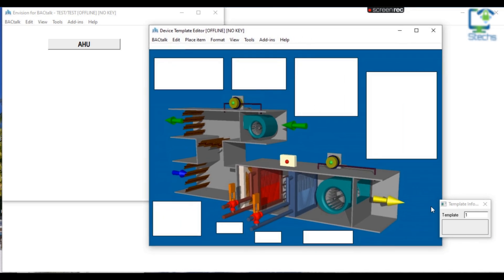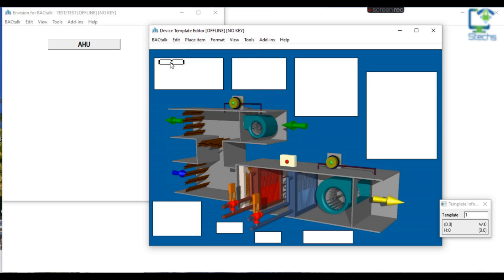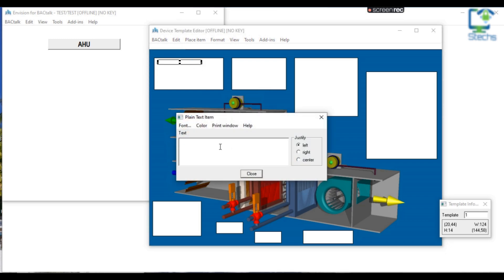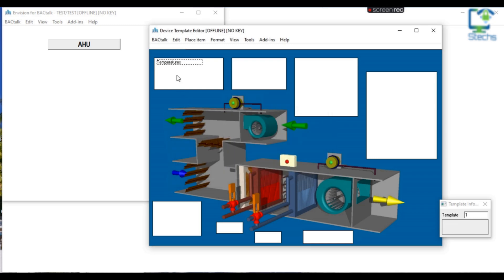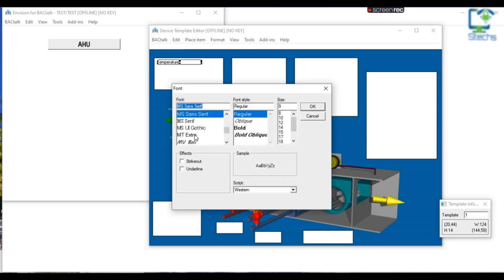We have plenty of images for various devices. For this AHU template I am choosing one file and clicking OK. Now you can see an image opened as a background with a picture of an AHU. To add text and parameters in the template, click on Place Item and select Plain Text, then click on the device template to paste the plain text template. Double-click on the plain text template to add text. Since the AHU controls temperature, I am giving "Temperature" as the heading text for the white column in the background image.